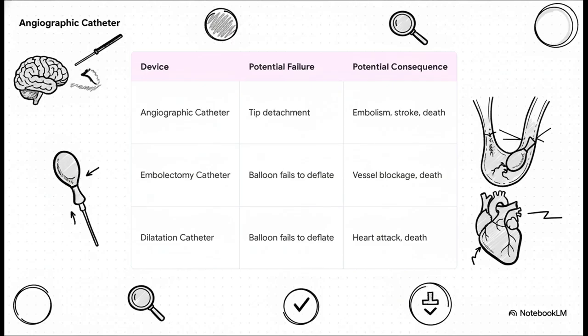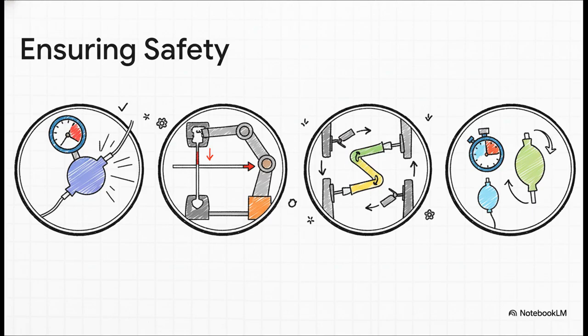So the direct response to those horrible risks is this: a massive battery of tests. Every single one of those engineering challenges we just talked about gets tested relentlessly. They test the balloon's burst pressure. They test the strength of the tip attachment. They put it on a machine to simulate millions of heartbeats. Every single aspect is measured, quantified, and validated to make absolutely sure it's safe before it ever goes near a patient.